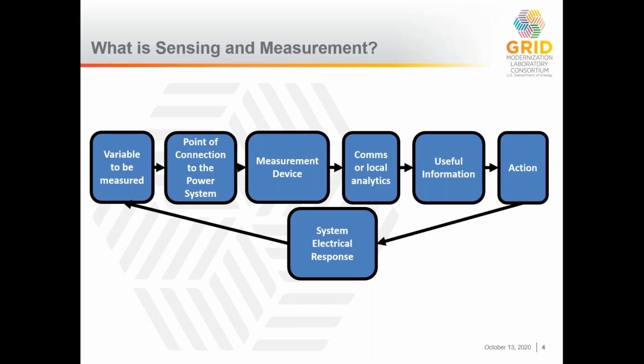You need to consider the accuracy at the point of connection as well, because everything connects to the system generally through some form of measurement device, be that a potential transformer or a current transformer, to get to that point.